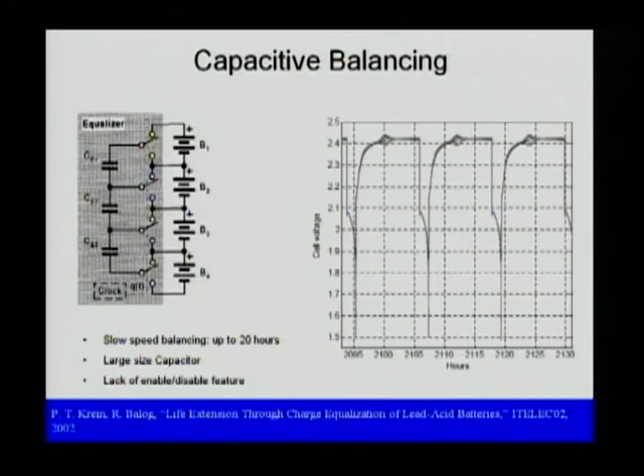At that point, any capacitor with a high voltage discharges into the lower-voltage battery, and when switched back on top, any capacitor with high voltage discharges to the battery while lower-voltage capacitors get charged by the battery. This is very energy efficient. However, due to the size limitations of the capacitors, it may take a long time to balance the batteries—some studies show it takes up to 20 hours for a very unbalanced system.